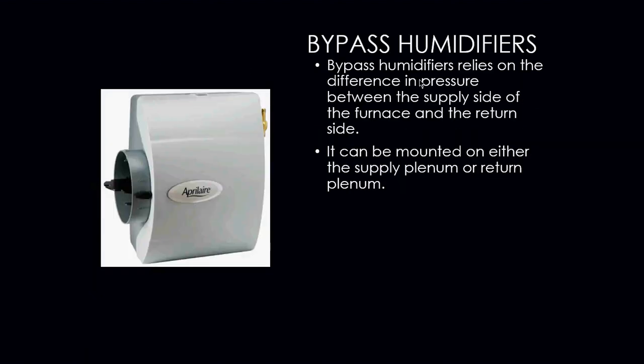Your bypass humidifiers, on the other hand, rely on the pressure difference between your supply duct and your return duct. When thinking about your supply and return, you need to think about the fan. Our return duct is creating a negative pressure. We are sucking the air back down to the furnace so that we can recirculate it through the heat exchanger and back out the supply duct. The supply duct is in a positive pressure because the blower is forcing and moving the air at a greater velocity. So by installing that bypass, we are using the pressure difference between those two ducts to bring moisture into the space.